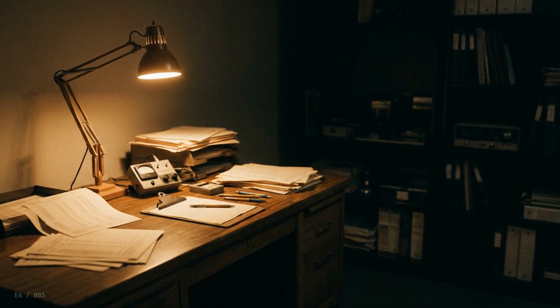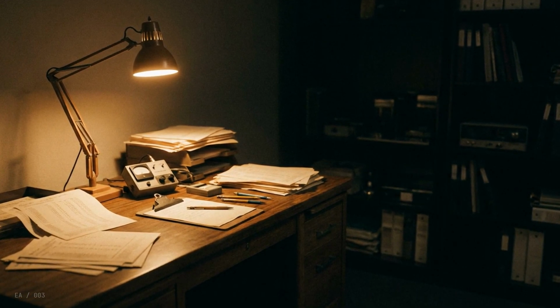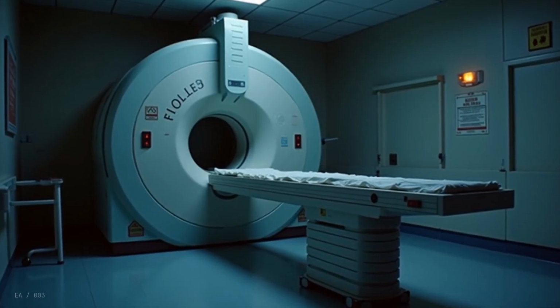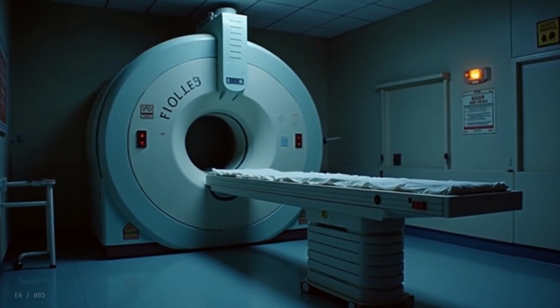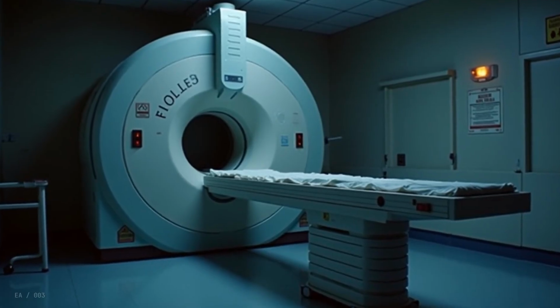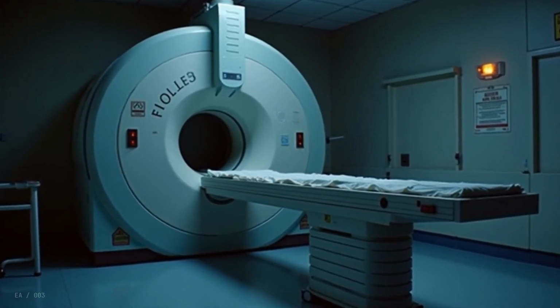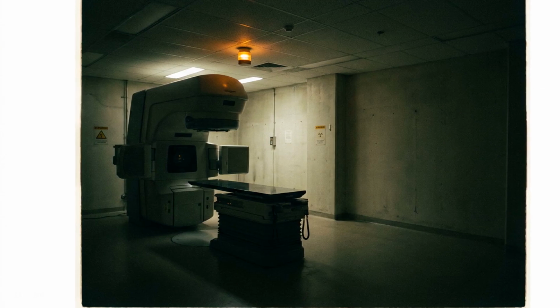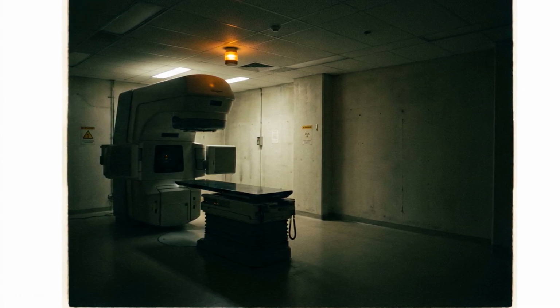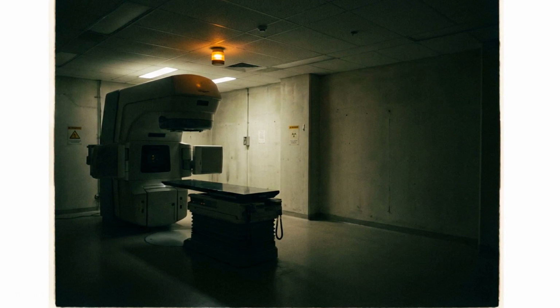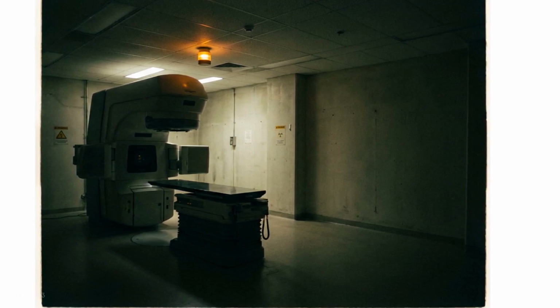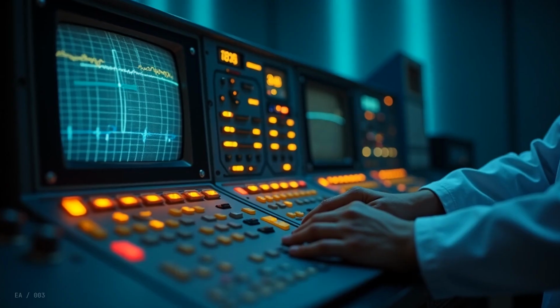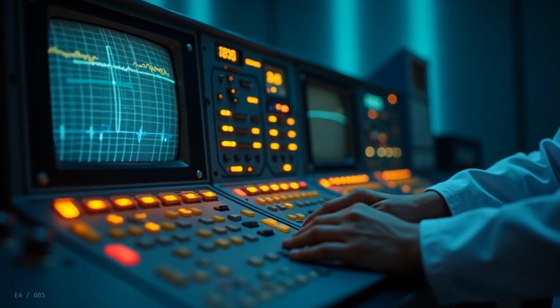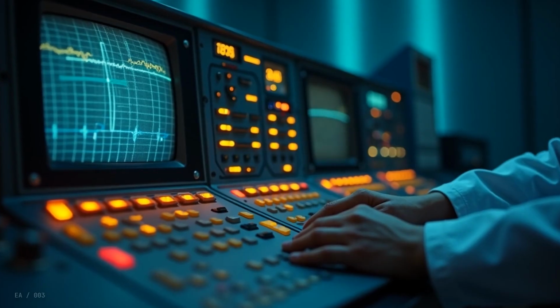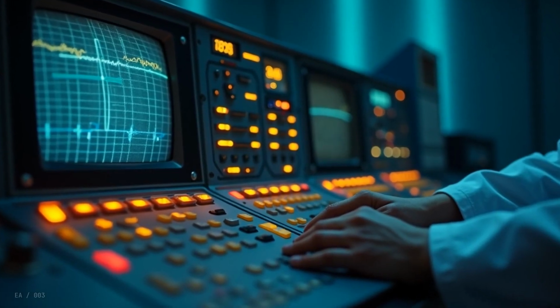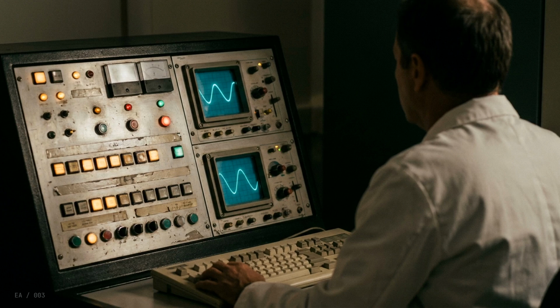The software, in those 8 seconds, had registered a mode change, then a second mode change, but had not waited for the plate movement to complete and reset. An internal flag called Class 3 got into a state the software's authors had never anticipated. The system believed the spreader plate was in X-ray position. It was not. It was still mid-motion, somewhere between the 2 end stops. The beam fired at full electron energy, 25 megavolts, no conversion, direct, unfiltered.